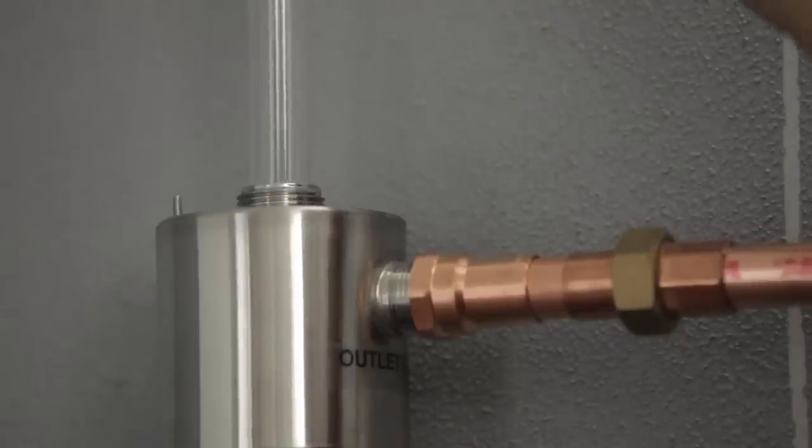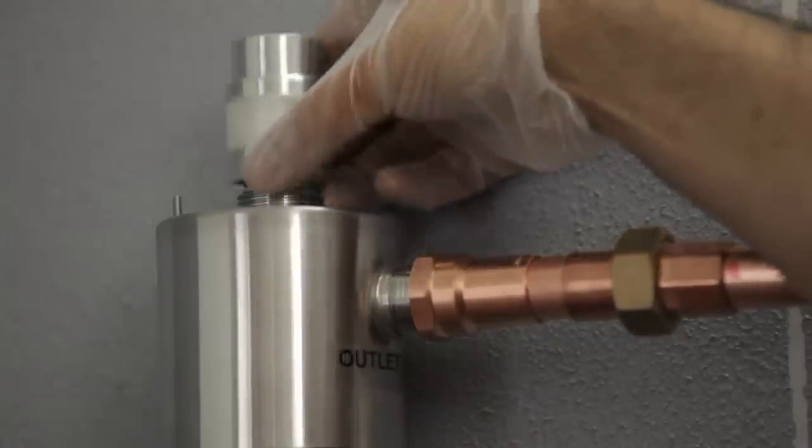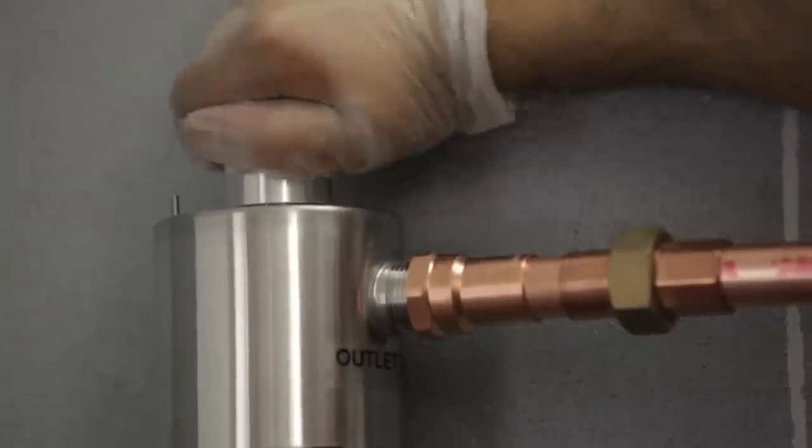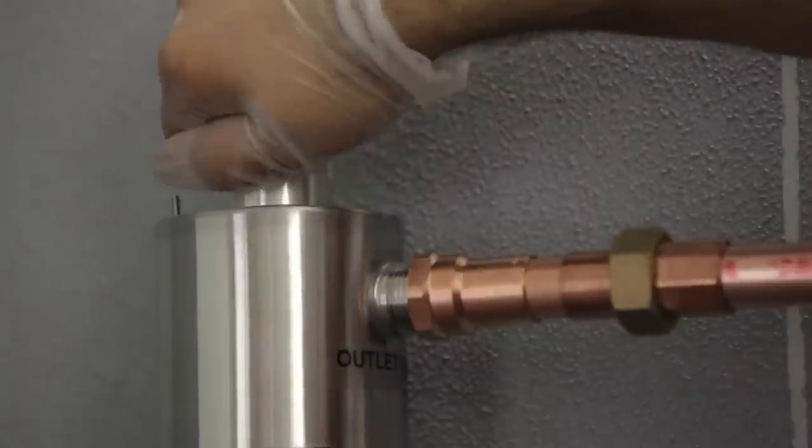Carefully slide the quartz dome with gland nut attached into the opening at the top of the UV chamber, and hand-tighten the gland nut into place. Do not over-tighten the gland nut, as it can break the quartz dome.